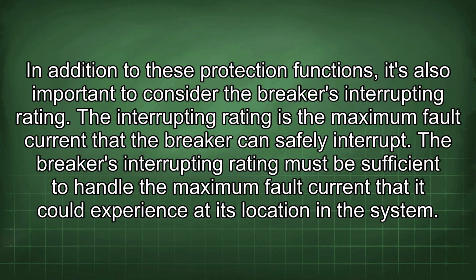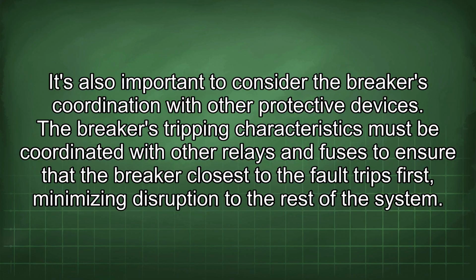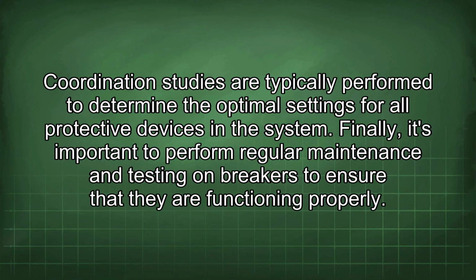In addition to these protection functions, it's also important to consider the breaker's interrupting rating. The interrupting rating is the maximum fault current that the breaker can safely interrupt. A breaker's interrupting rating must be sufficient to handle the maximum fault current that it could experience at its location in the system. It's also important to consider the breaker's coordination with other protective devices. The breaker's tripping characteristics must be coordinated with other relays and fuses to ensure that the breaker closest to the fault trips first, minimizing disruption to the rest of the system. Coordination studies are typically performed to determine the optimal settings for all protective devices in the system.